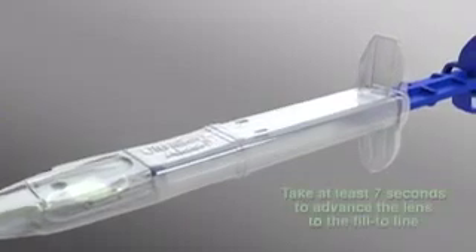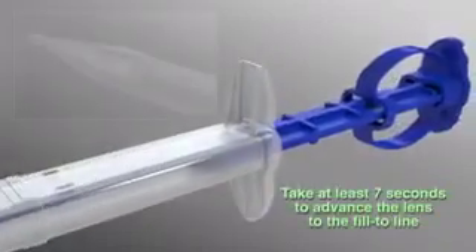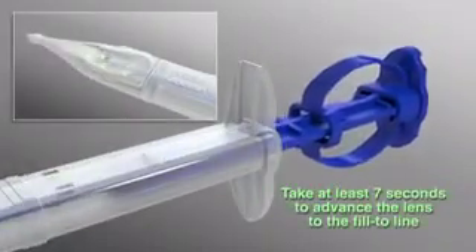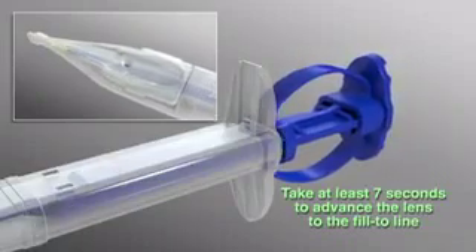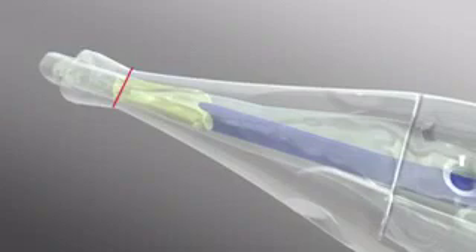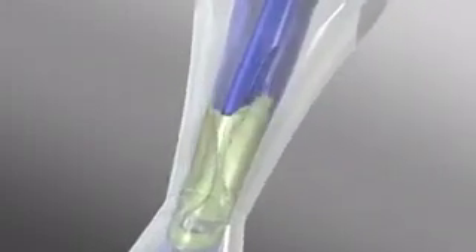Finally, take at least 7 seconds to gently fold the lens by advancing the plunger forward in one smooth, continuous motion until the front edge of the optic is even with the fill-to line. It is important to not advance the plunger abruptly, as improper folding and lens damage may occur. At this point, check the plunger position under the microscope.